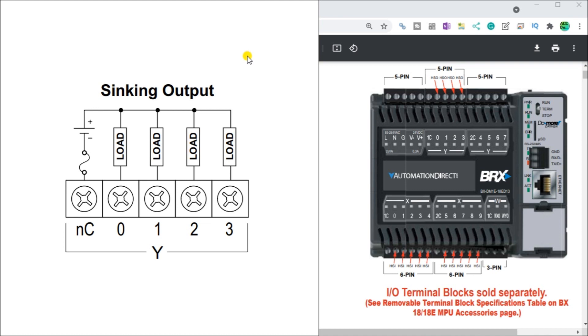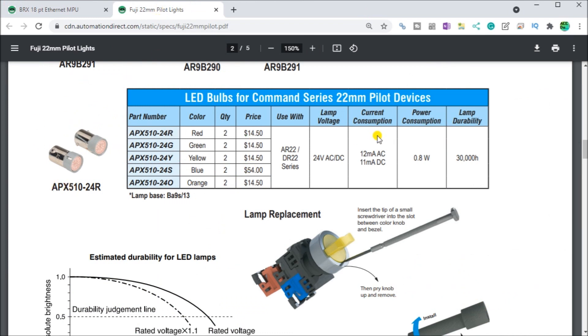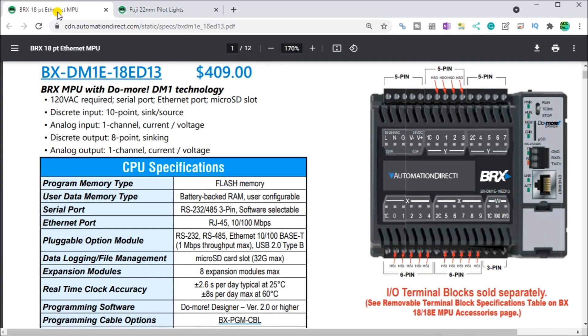We're going to control two LED lamps. Looking at our Fuji LED lamps, the current consumption is 11 milliamps for each one. We have two of them, so we have a total of 22 milliamps to control. Remember, we can have 500 milliamps per common or two amps per total circuit — and we're well below that. So we're good for the amperage. It's always good to check the load and make sure.